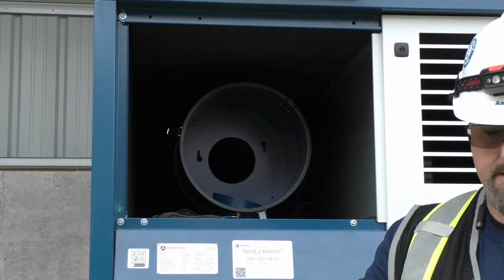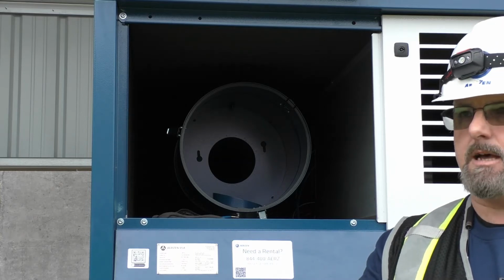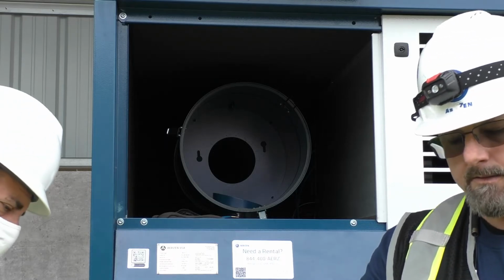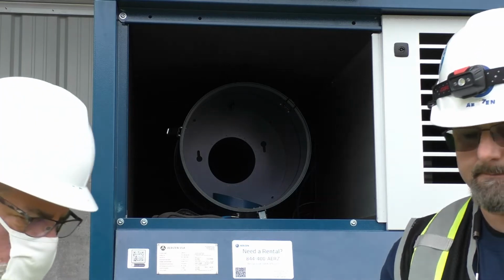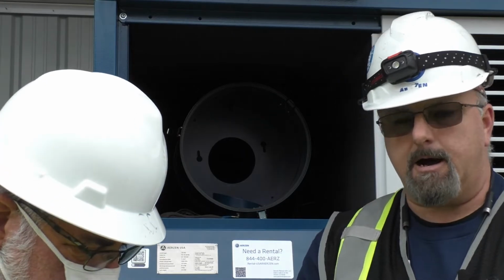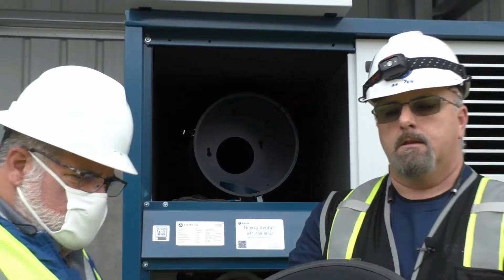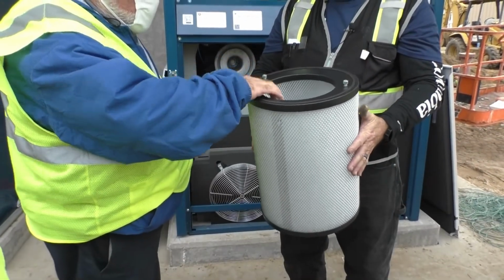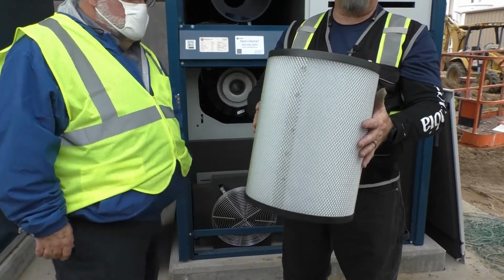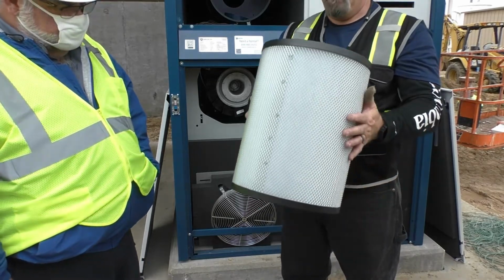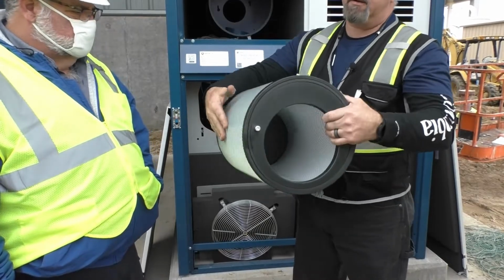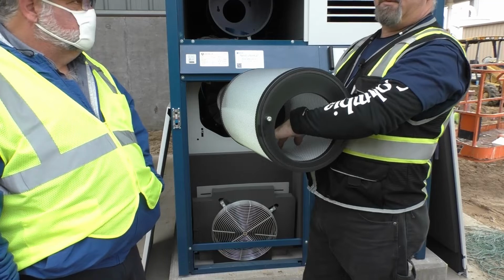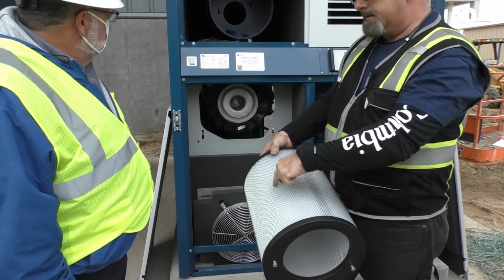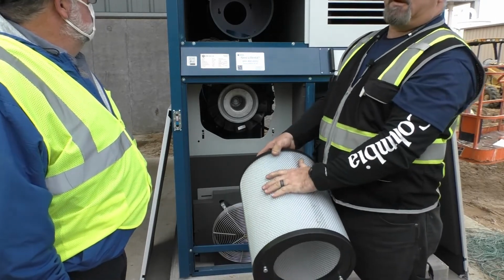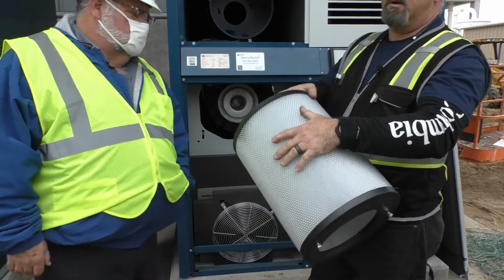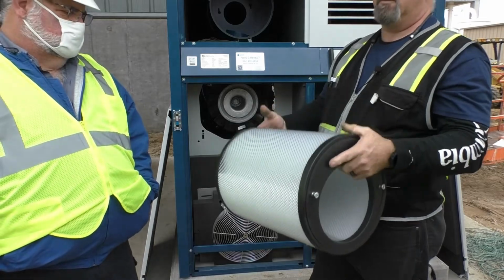Give it a slight twist to take it out, slight twist to lock it. Now if when you put the filter in, it's too loose, you can tighten these 2 screws up slightly, but it's not going to do a whole lot because they're only glued on the back of the piece. Now your filter, if you've ever seen the polyfill that is in like quilts or blankets, that's basically what this filter media is. So hence why it is not cleanable, because if you saturate it with water, just like polyester, it will shrink.